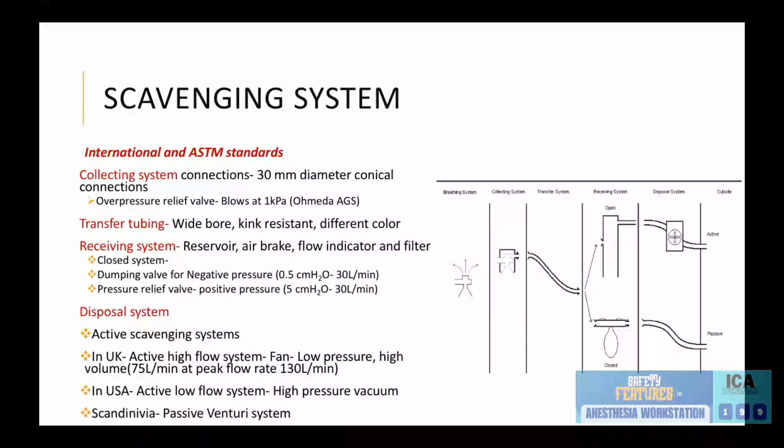In the UK, what is present is a high flow active scavenging system. In the US, what is present is a low flow active scavenging system. What we have is also a fan-based scavenging system in our hospital. In Scandinavia, they have passive venturi systems.